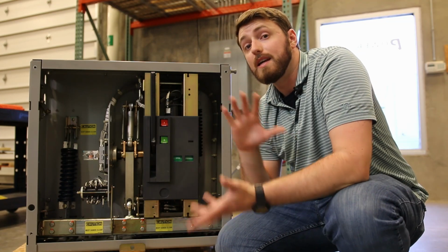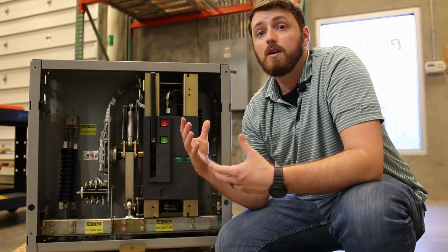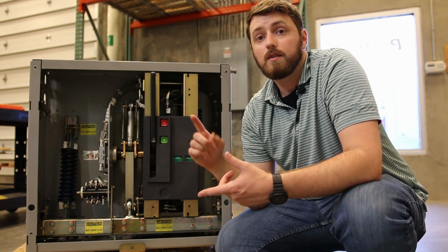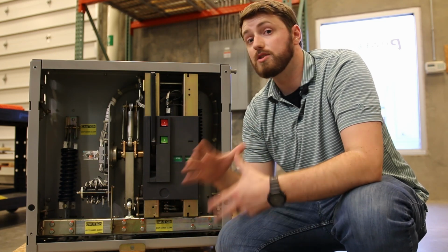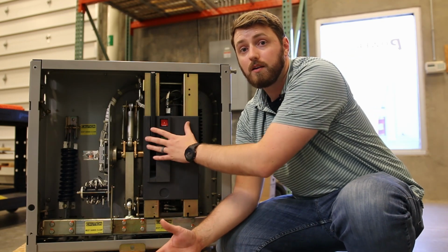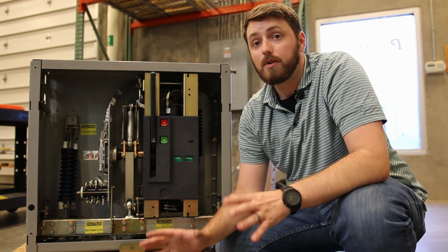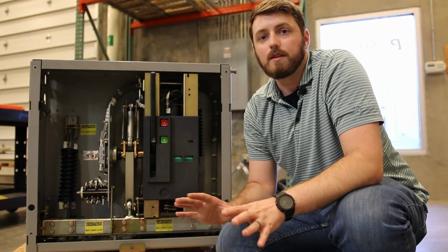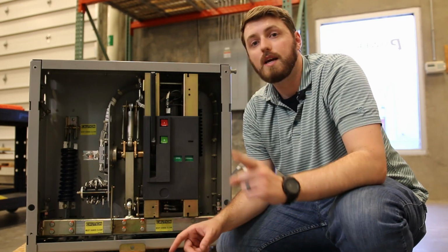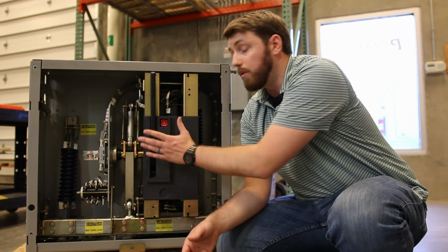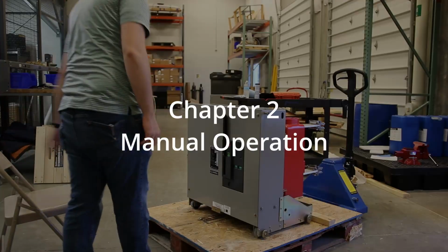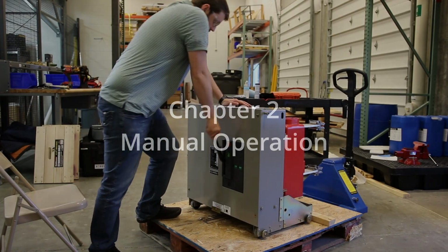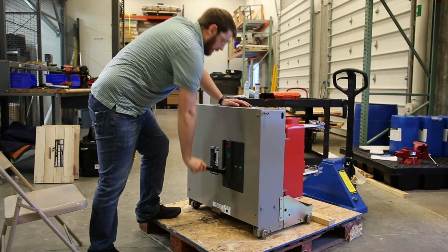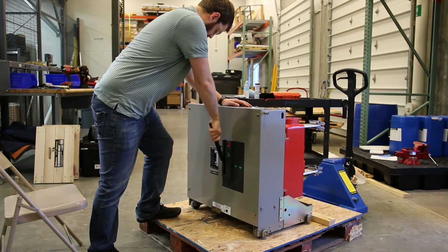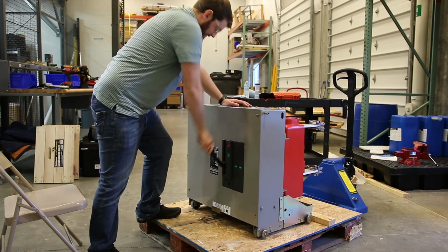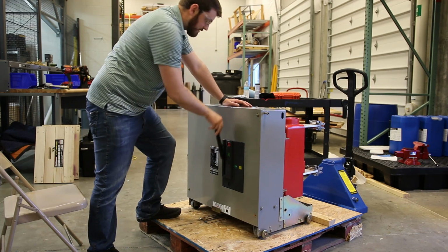The CTs are going to be located in the cell, and so is the protection. For medium voltage equipment, the overcurrent device is going to be a relay located somewhere in the switchgear. It's not in the breaker. So we have to make sure that the breaker operates well by itself, independently. Testing the relays, the protection devices, is a completely separate external thing. What we're doing here is just testing the breaker. We're going to manually close this, so we need to run the charging handle. You're going to charge and charge and charge until it makes a loud, satisfying click.